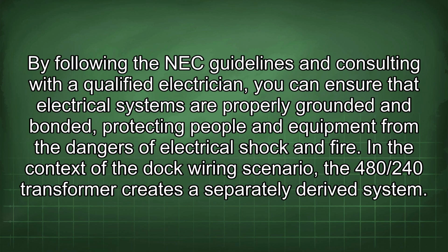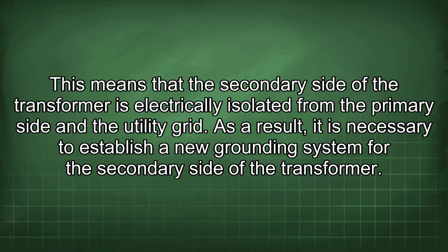By following the NEC guidelines and consulting with a qualified electrician, you can ensure that electrical systems are properly grounded and bonded, protecting people and equipment from the dangers of electrical shock and fire. In the context of the dock wiring scenario, the 480/240 transformer creates a separately derived system. This means that the secondary side of the transformer is electrically isolated from the primary side and the utility grid. As a result, it is necessary to establish a new grounding system for the secondary side of the transformer.